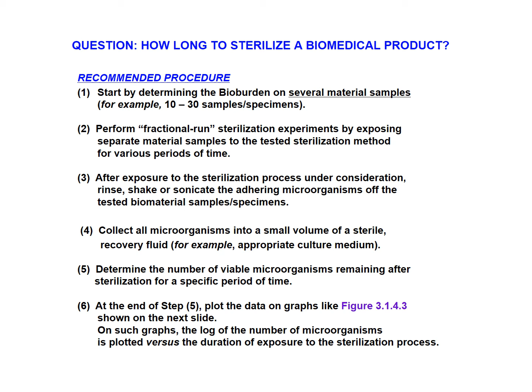At that point, plot the data on graphs like figure 3.1.4.3, which is shown on the next slide. This graph is used to determine the effective duration of material exposure to sterilization. It is a busy graph. Let us focus on the important aspects. First and foremost, the y-axis of this graph is a log plot of the number of microorganisms. The x-axis is the duration, the time interval of the exposure of the particular pathogens to the sterilization method. Let's say that we start with a particular bioburden in the order of 10 to the 6th, or somewhere between 10 to the 5th and 10 to the 6th pathogen microorganisms.